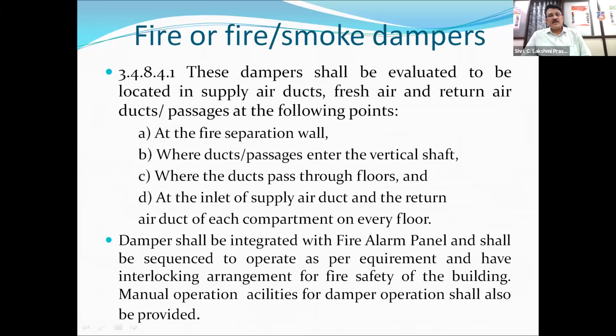Then dampers, where they should be located, it is all given: at the separation wall, where ducts enter the vertical shaft, where the ducts pass through floors, at the inlet of the supply air duct and return air duct. Dampers shall be integrated with the fire alarm and shall be sequenced to operate as per requirement, and have an interlocking arrangement for fire safety of the building. Manual operation for damper operation shall also be provided.